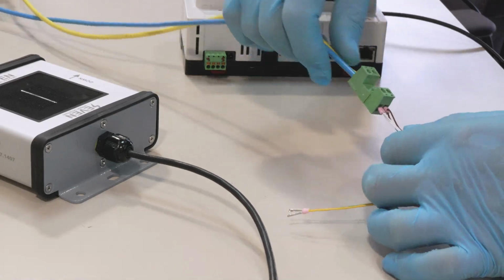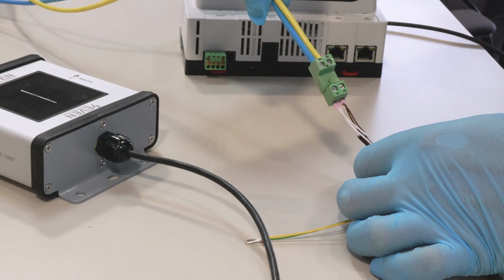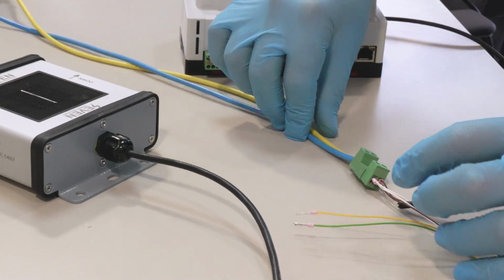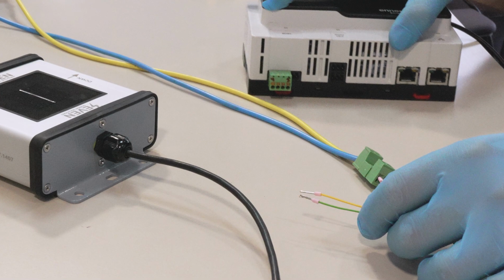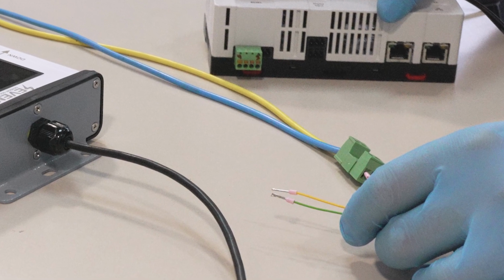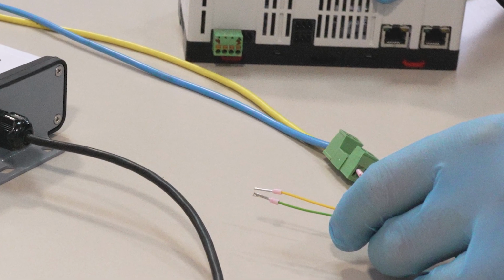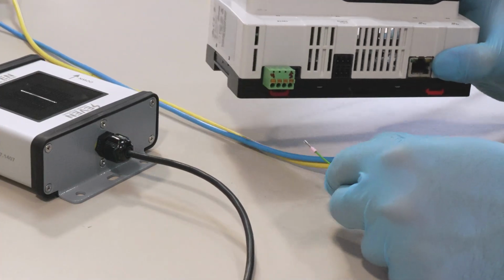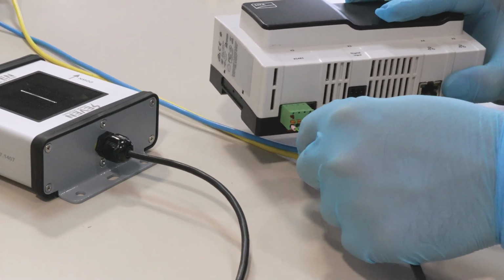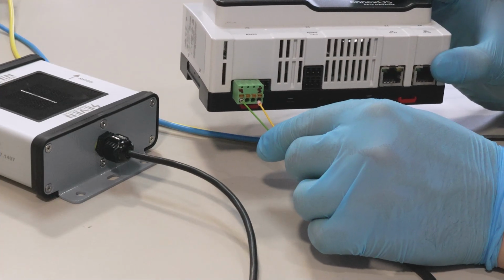7 sensors work with 12 to 30 volt DC, and the recommended voltage value is 24 volt DC. The green and yellow wires are connected to pins 1 and 4 of the RS485 port of the SMA data logger. The green wire is connected to input 1, and the yellow wire is connected to input 2.